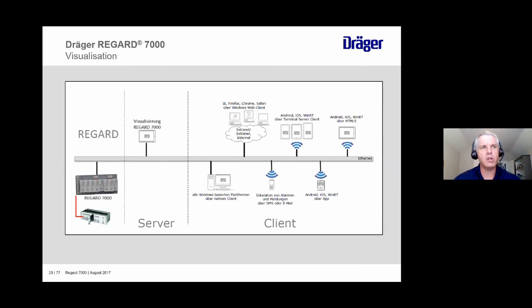So this last screen talks about the networking capabilities of the Regard 7000 through that Modbus TCP/IP output module. If a customer buys a Regard 7000, most of them will have the Modbus TCP/IP output. Once you've got that output, you just connect to it, and that's basically Ethernet. So through a multitude of devices, you can hook onto that. I know we're quoting a big project right now for Airgas, and that's one of the features that they potentially could like. They're not going to use it right now.